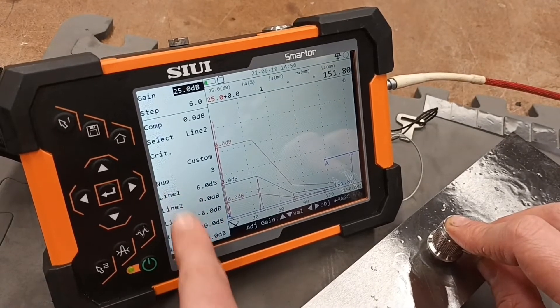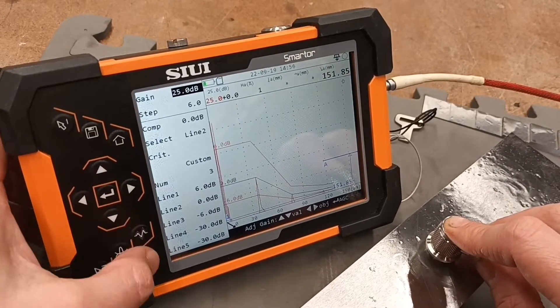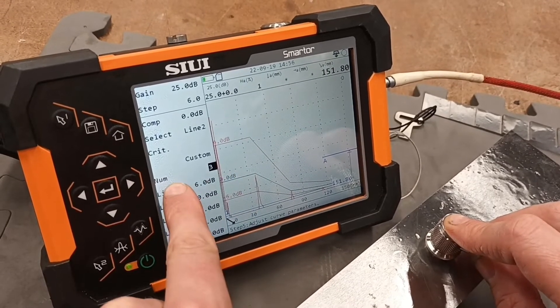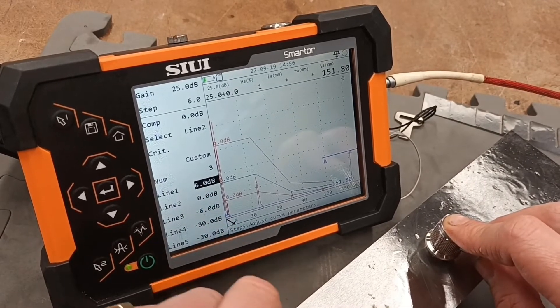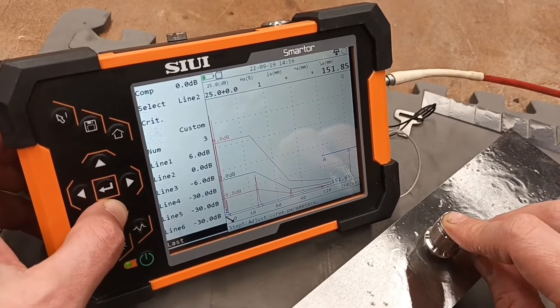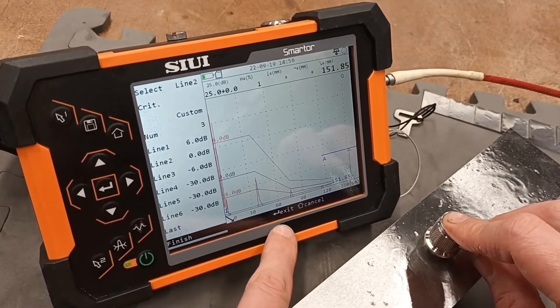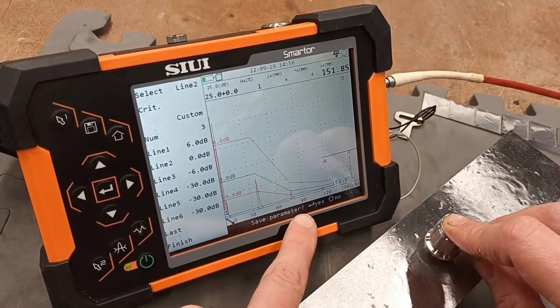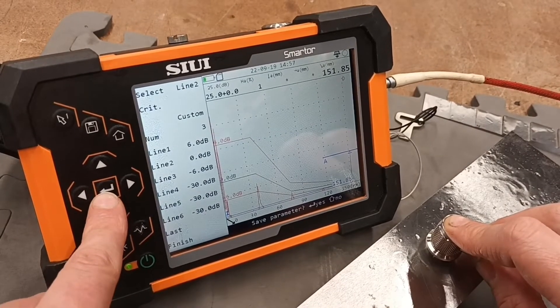We can add additional curved lines. We can scroll down here and add more or take away, and then we can individually adjust the dB, adding or taking away on each individual line. That's not necessary in this setup. We can scroll down and finish. It'll ask us to save the parameters — yes or no — by hitting those buttons. That's the yes button, that's the no button.